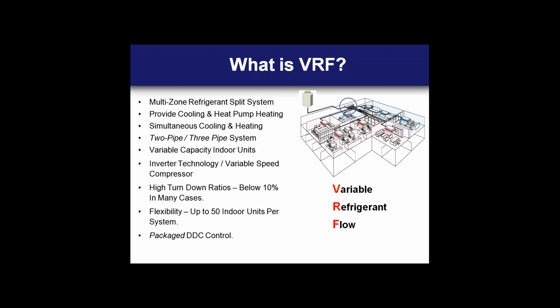Among this VRF, particularly commercial class equipment, all of these systems have the capability to provide cooling and heat pump heating operation, and with a far greater extended range that we'll illustrate later in the presentation. Also unique to these systems is the ability to provide simultaneous heating and cooling, where some zones can be in cool and others in heat, and energy is transferred or shared via that refrigeration network, increasing the effective efficiency of the system in those simultaneous modes.